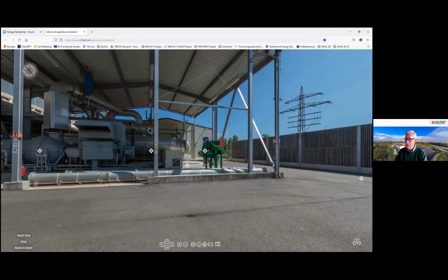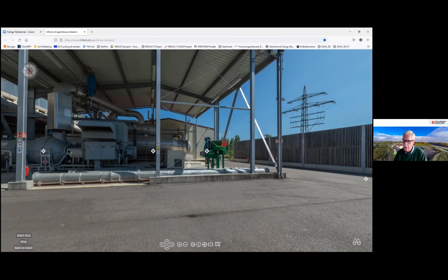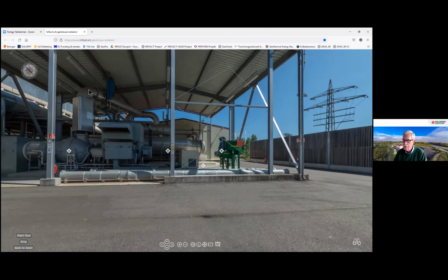And this is the vaporizer. On top, we have a so-called demister, which takes care that we do not have any fluid drops in the vapor, and this would have a negative impact on the turbine. So the isopentane vapor is flowing on top into our turbine, rotating the turbine.